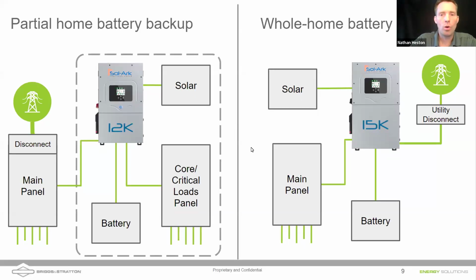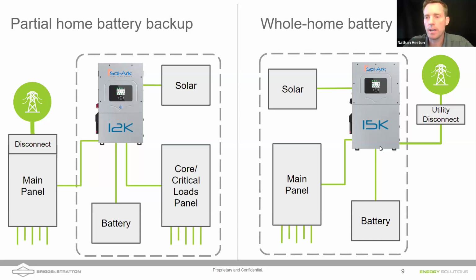And then in a grid-down situation, your batteries would supply power to that critical loads panel. With a whole home backup, it's different - there is a utility disconnect, but all of the power can pass through that Sol-Ark 15K. That's the advantage of having 200 amps of pass-through on the Sol-Ark 15K, and then you would back up the entire loads panel of the house.